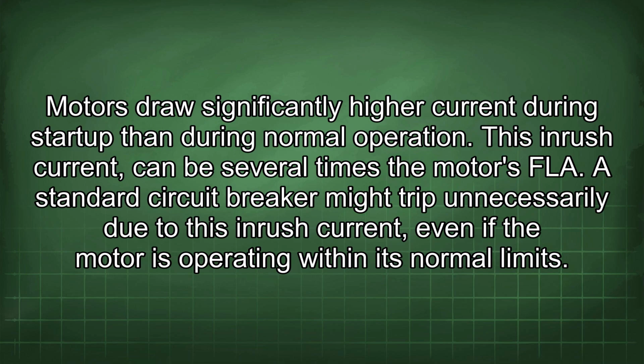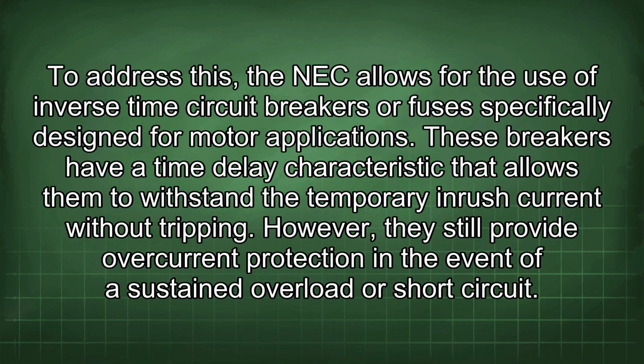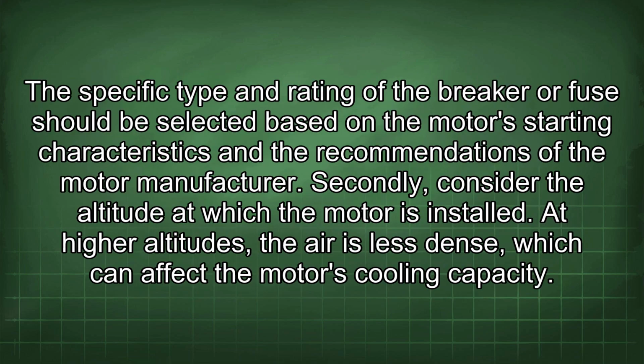normal limits. To address this, the NEC allows for the use of inverse time circuit breakers or fuses specifically designed for motor applications. These breakers have a time delay characteristic that allows them to withstand the temporary inrush current without tripping. However, they still provide overcurrent protection in the event of a sustained overload or short circuit. The specific type and rating of the breaker or fuse should be selected based on the motor's starting characteristics and the recommendations of the motor manufacturer.